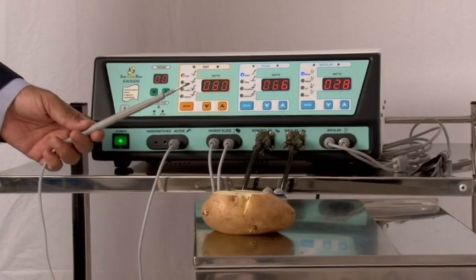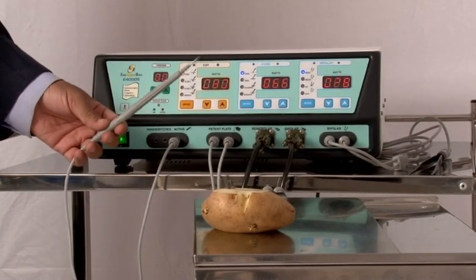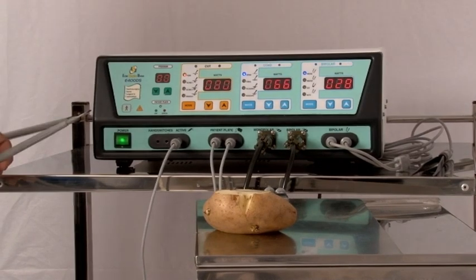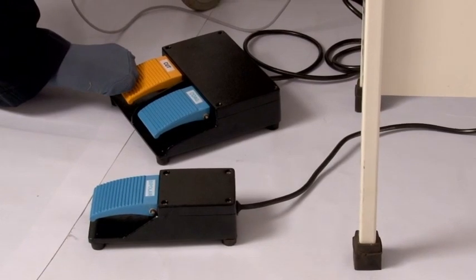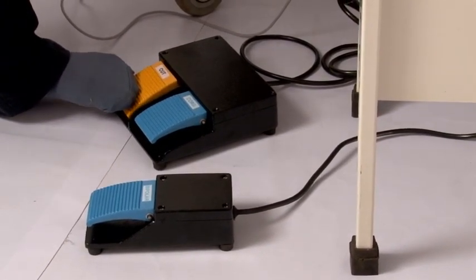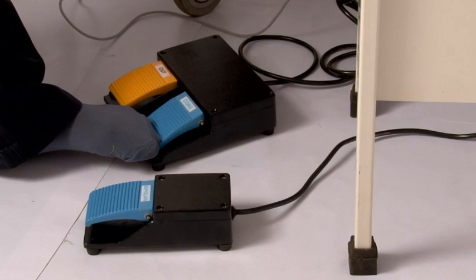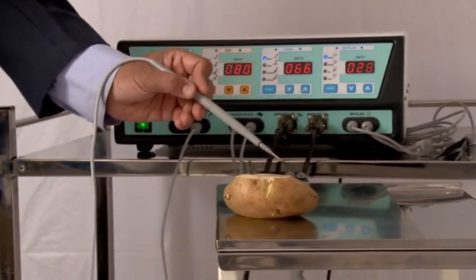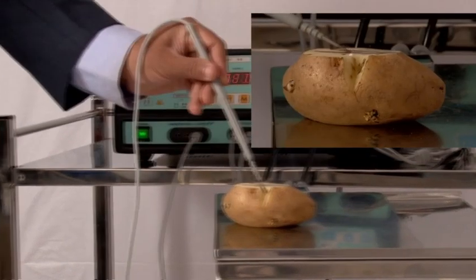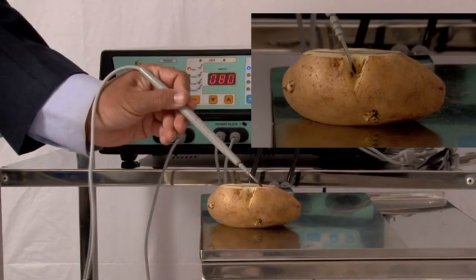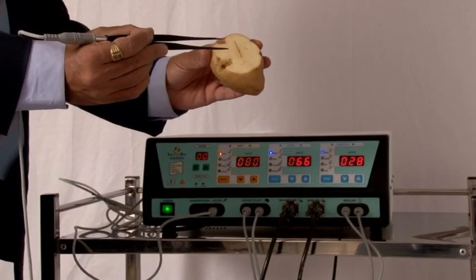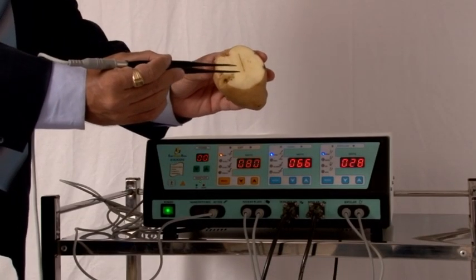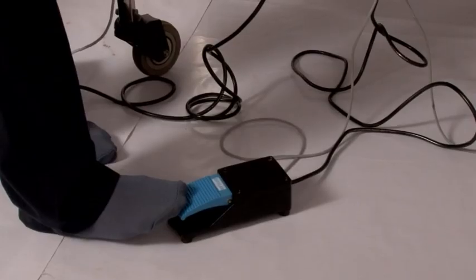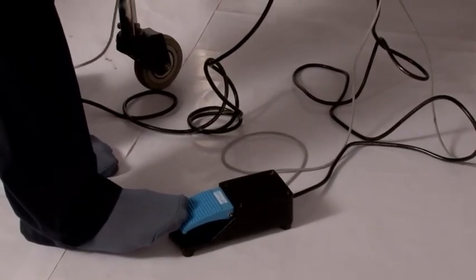In monopolar mode, we can also use reusable chuck handle. This handle is operated by monopolar foot switch. Yellow pedal is for cut output and blue pedal is for coag output. It cuts like a knife in the butter and coagulates from a distance without touching the tissues. Bipolar forceps is used for bipolar coagulation and it is operated by bipolar foot switch.